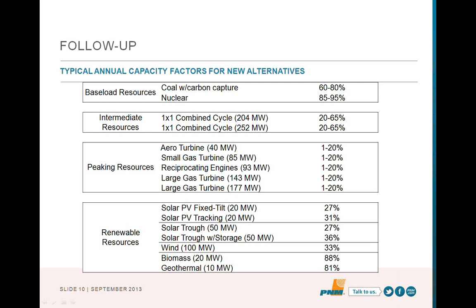For solar fixed tilt and for wind, we've got data that's based on existing facilities. For the solar PV tracking, which is what we're saying is part of the good cost-effective resource mix for San Juan capacity, what we have is bids that were received. We're going to be building that technology next year. But because in that case we had bids, not data, we spent a long time examining what if the bids aren't right. We looked at the range of what the capacity on peak might be that would still make that selection. If in isolation all we're looking at is capability on peak, we still would make that selection even if the single axis tracking looked like fixed tilt. So I know the single axis tracking is going to be at least as good, should be a lot better than fixed tilt in terms of contribution on summer peak.